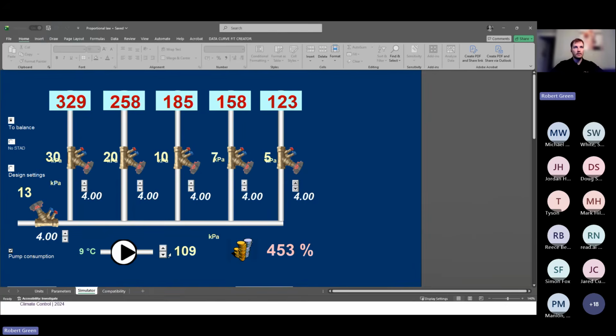Okay, brilliant. We are back to, let's push this pump head back down. Let's get ourselves back to 100% on this last unit, or thereabouts. And I'm now going to exploit the proportional rule. What it states is any change I make upstream affects all units downstream in proportion. So in essence, what I wish to do is change units downstream until I get these two units in proportion to each other. So now I'm going to reduce the opening here until these two units have the same flow, or as close as we can get it.